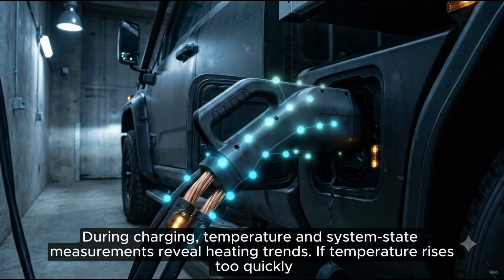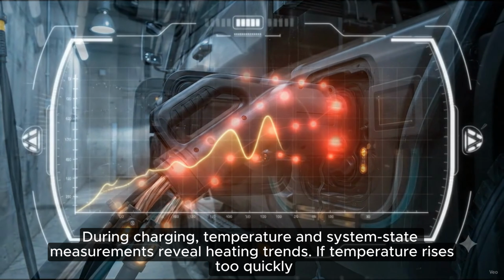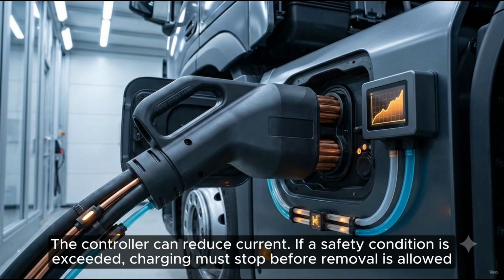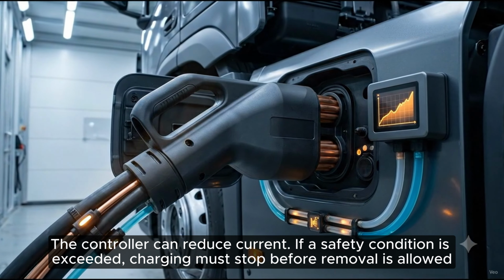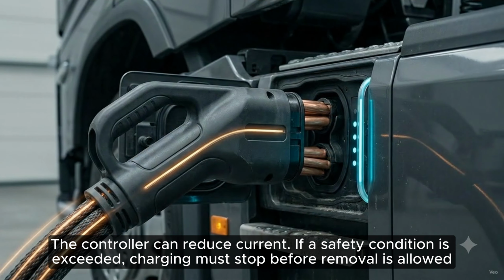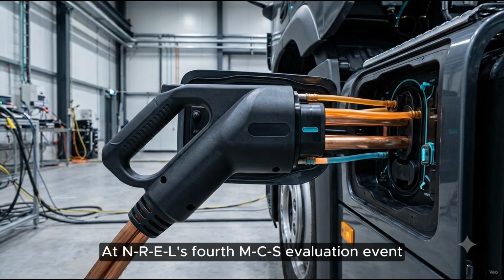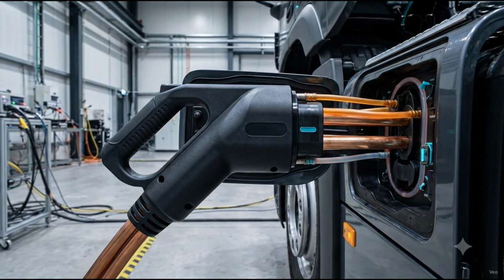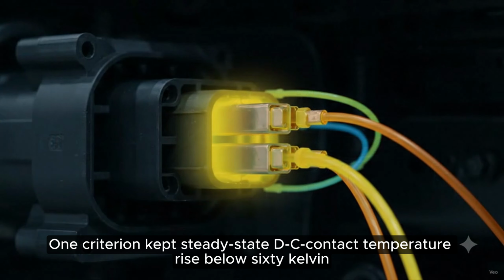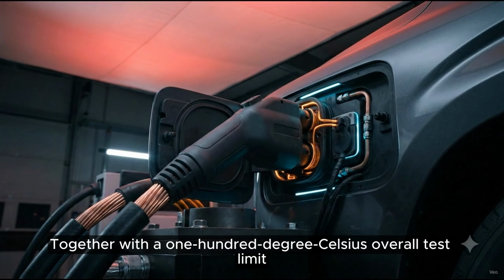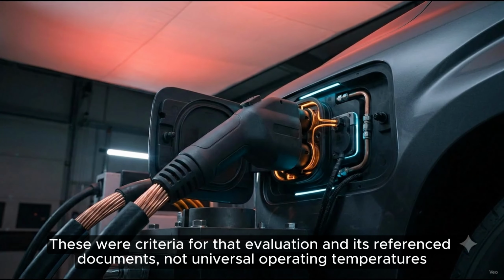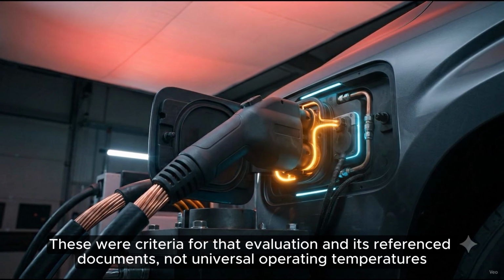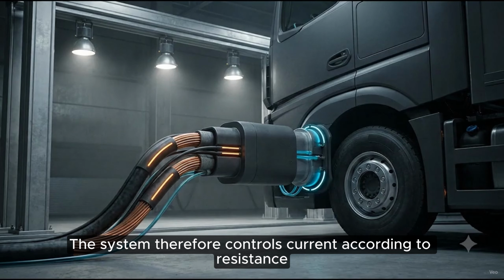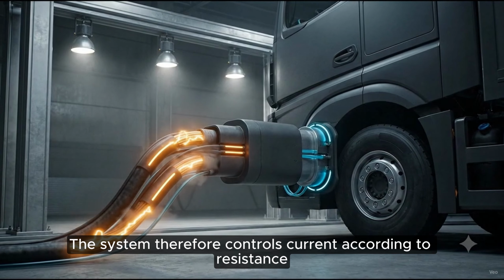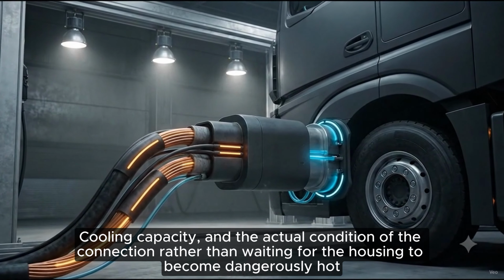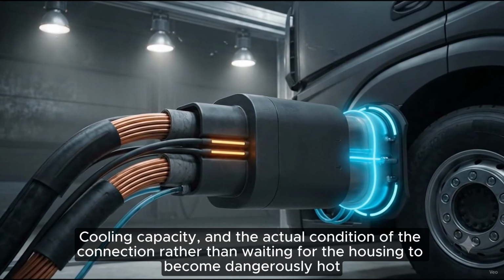During charging, temperature and system state measurements reveal heating trends. If temperature rises too quickly, the controller can reduce current. If a safety condition is exceeded, charging must stop before removal is allowed. At NREL's 4th MCS evaluation event, one criterion kept steady-state DC contact temperature rise below 60 Kelvin, together with a 100 degrees Celsius overall test limit. These were criteria for that evaluation and its reference documents, not universal operating temperatures. The system therefore controls current, according to resistance, cooling capacity, and the actual condition of the connection, rather than waiting for the housing to become dangerously hot.